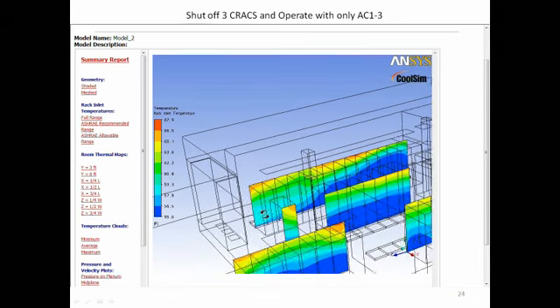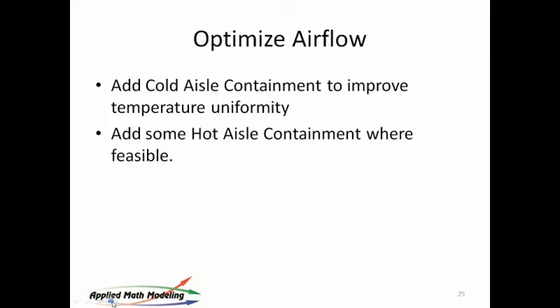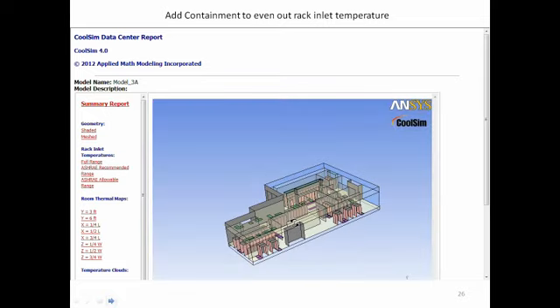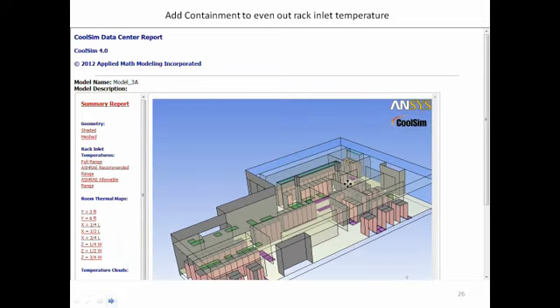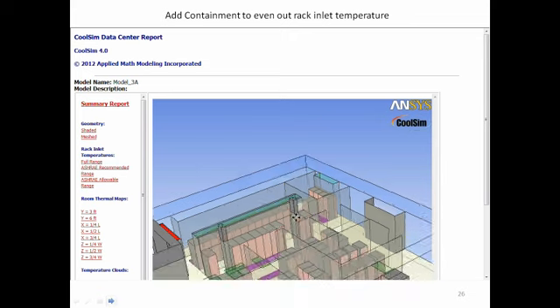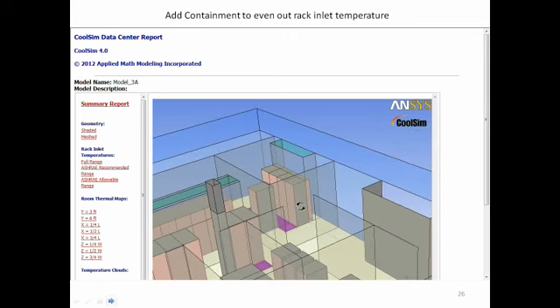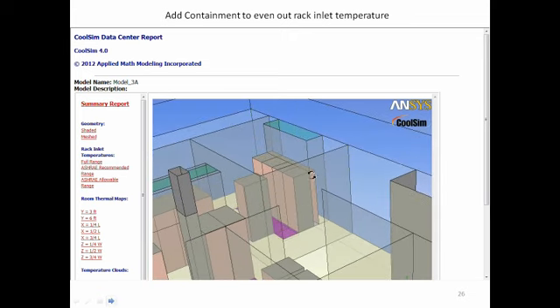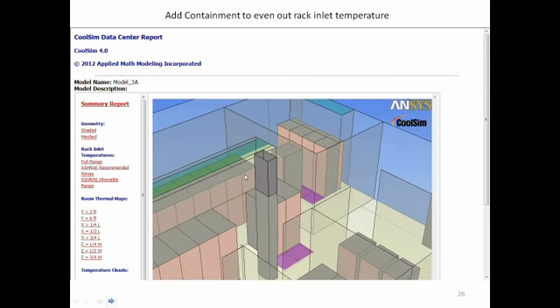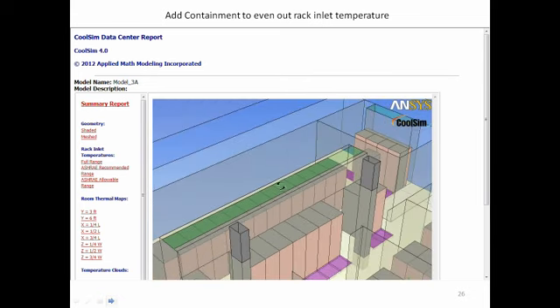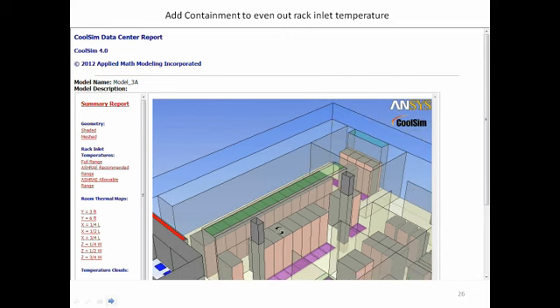Very typical. So in the next model, we use a little bit of cold aisle and a little bit of hot aisle, a little bit of both. Fortunately, in this room we have a ceiling plenum, and that helps with respect to hot aisle in a few key areas. For example, here's a set of equipment up against the wall with ceiling plenum return grills above. Very nice place to put some curtains. Another natural hot aisle in this room is right here.